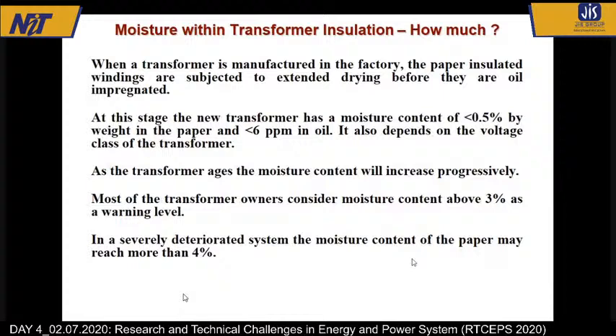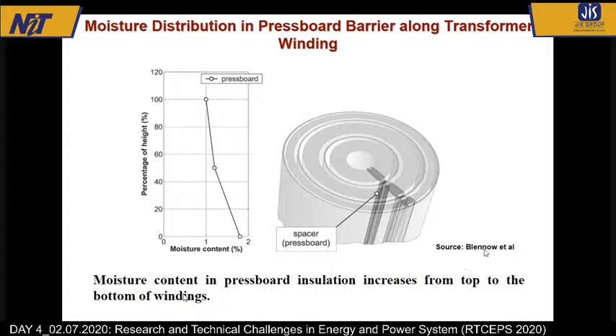As I was telling about how much the moisture content will be, in the second paragraph you can see that at the time of installation, generally it is less than 0.5% by weight in the paper and less than 6 parts per million in oil. This is the typically expected value. But as the transformer is used, the moisture content can reach 3%, then we say this is the warning level. And at the bottom you can see that if it goes around 4%, then the condition is very poor. So what we are trying nowadays is to develop monitoring or testing techniques by which we try to measure this moisture content in paper. This source is given.